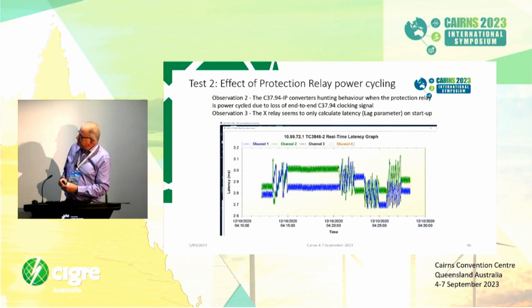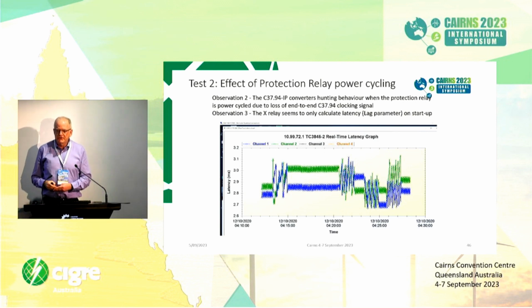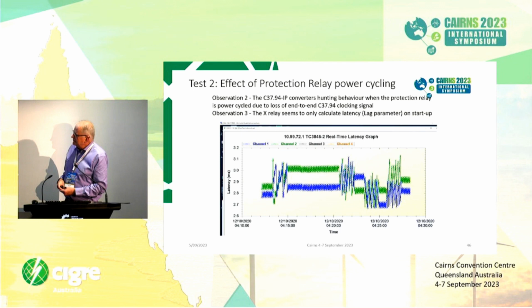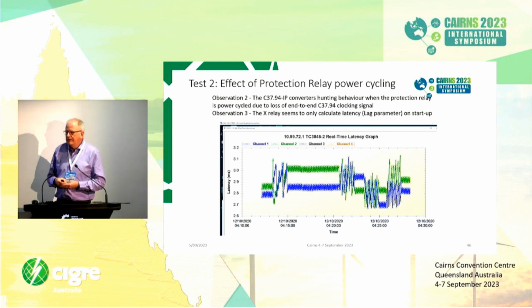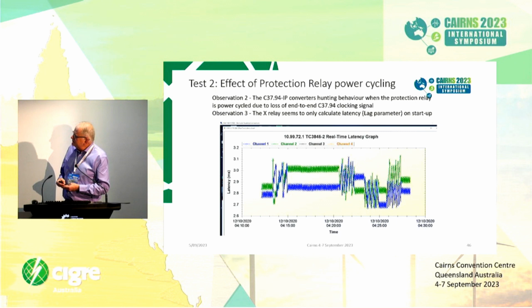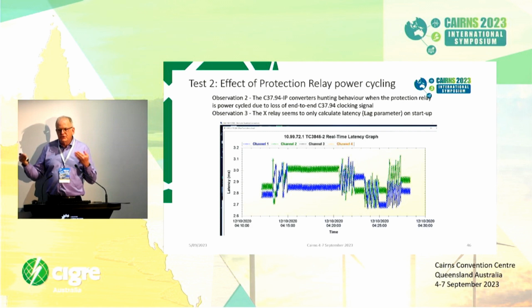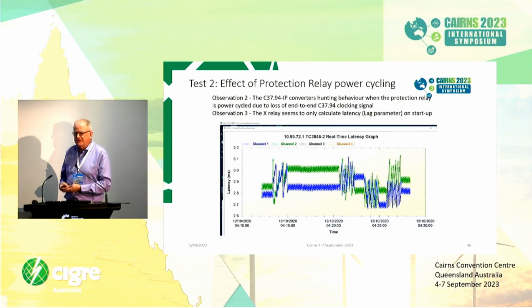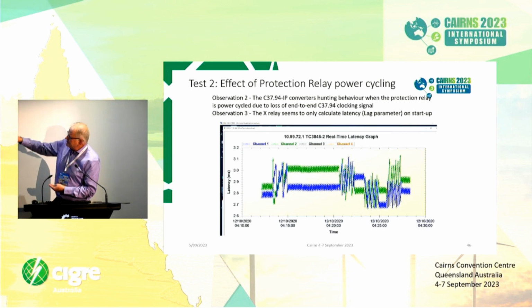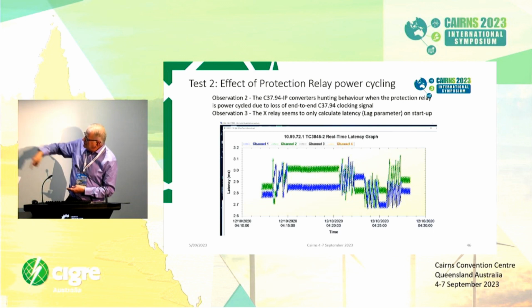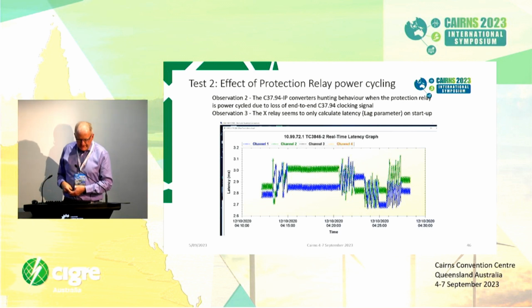But what happens, this is during that test on the previous slide, when we power cycle the protection relays, we actually break that loop back of the timing signal in the protection relays at each end. And when we break the loop back, the observation is that the C37.94 converters go into a bit of a free-running time mode, searching for a synchronisation signal to be returned. So that's what those larger deviations are for the four sections of the graph there.